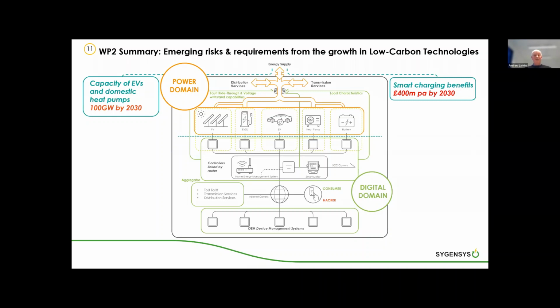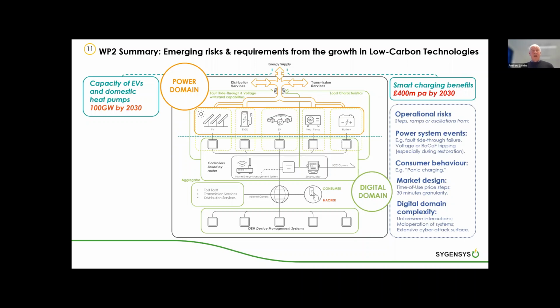But also, sadly, this opens up the opportunity of control by hackers. And alongside this, all of the device manufacturers may also have mechanisms to provide services into these devices. Typically, that might not be direct control, but it could, for example, be software updates. This introduces a number of different operational risks. So how will these systems perform during power systems events? What are their fault ride-through characteristics? And we'll talk more about RoCoF and voltage ride-through characteristics.